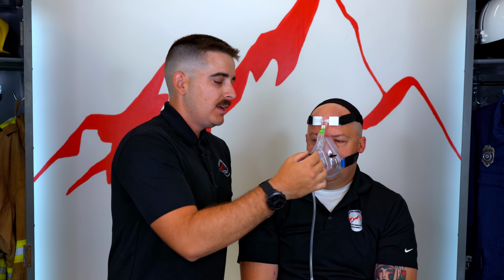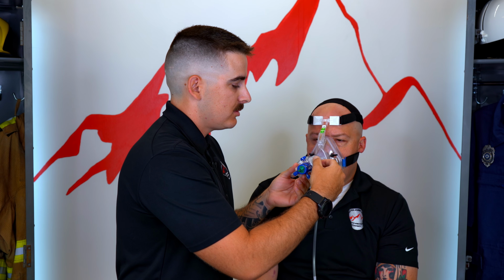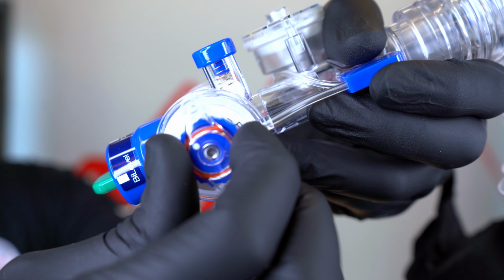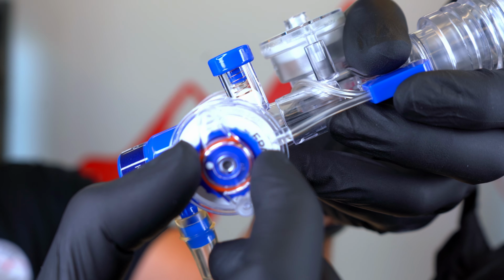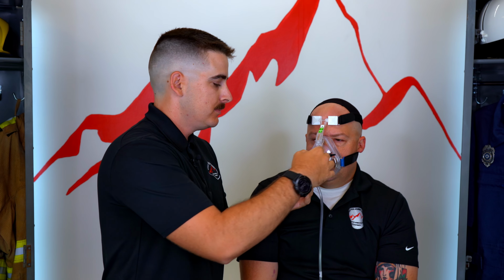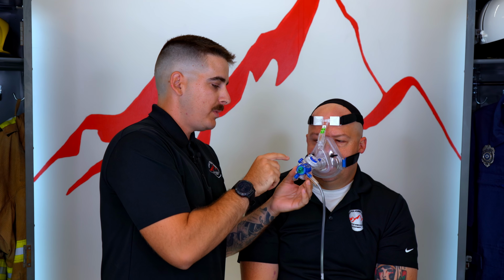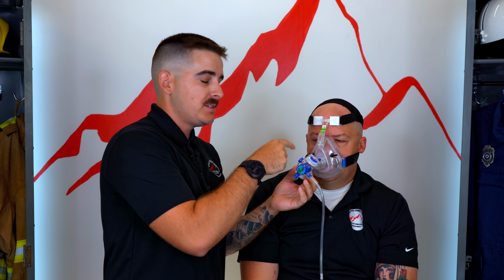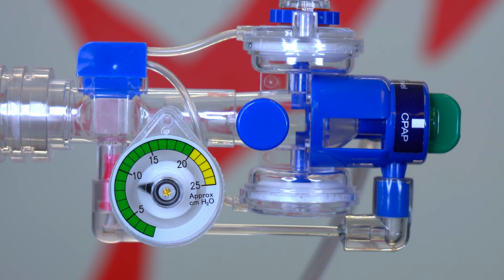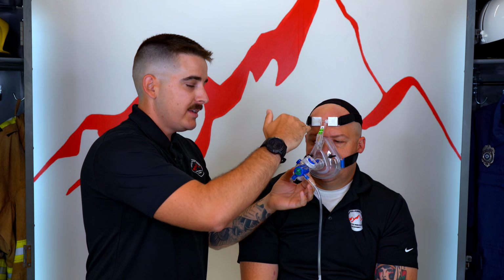And so right now, I see that Chris has an IPAP, inspiratory pressure of 10, and I want to set the EPAP. And so this is done with this dial here. And I'm going to adjust it until I get 5 on my EPAP. And that will just show me that when he breathes in, I look at the number that the manometer reaches. It's reaching 10 centimeters of water pressure. That's my IPAP. And then at rest, it will rest at another number, and it's resting at 5 centimeters of water pressure. That's my EPAP, or my PEEP, okay?